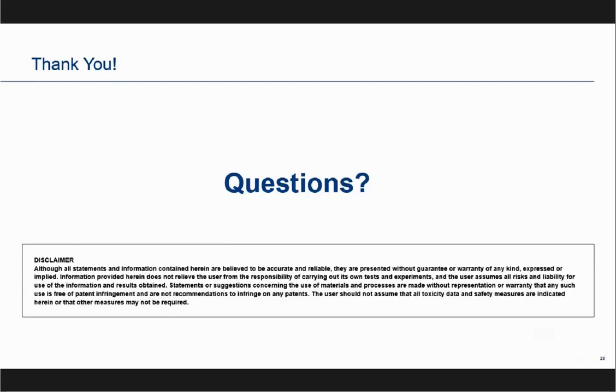Lots of good questions came in during the presentation. Thank you, everybody. Several of you picked up on the fact that we were talking about capacity control from 20 to 100%, and pointed out that Copeland digital scrolls typically unload to 10% capacity. That's a parameter setting Julie was talking about. The unit leaves the factory with the minimum capacity setting at 20%, with a 20-second digital cycle, but both of those parameters are adjustable. You can have a shorter or longer digital cycle, and you can take it down to 10%. There are details in our application engineering bulletin 1412, which talks about those parameters and considerations to have. But again, those are just factory settings. If you want a more aggressive digital cycle, you should probably consult with your application engineer before doing that. Do you have anything to add, Julie? No, I think that's great.